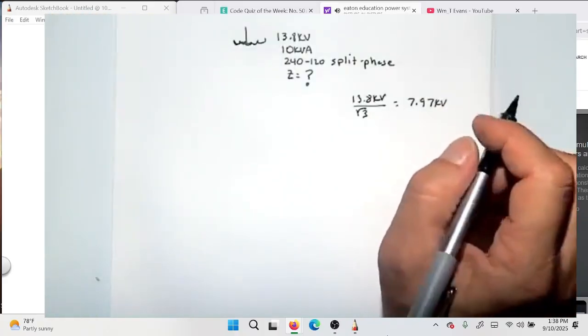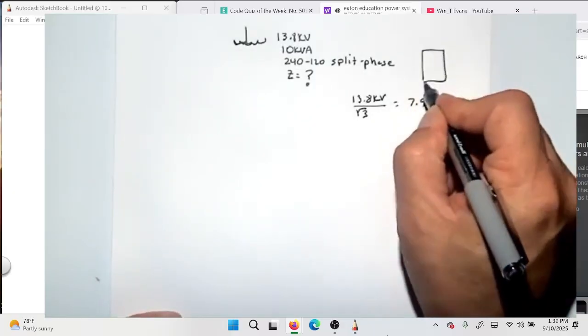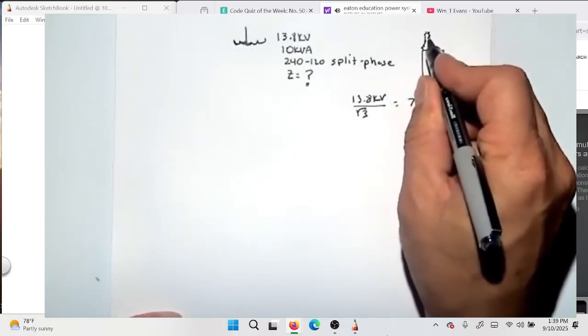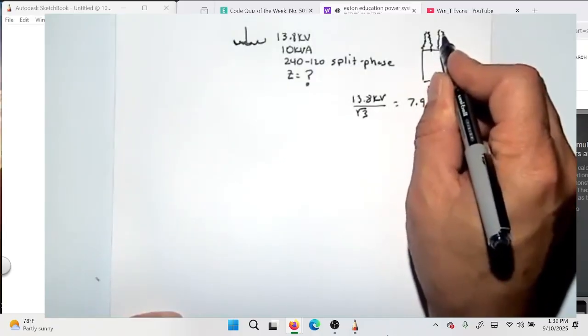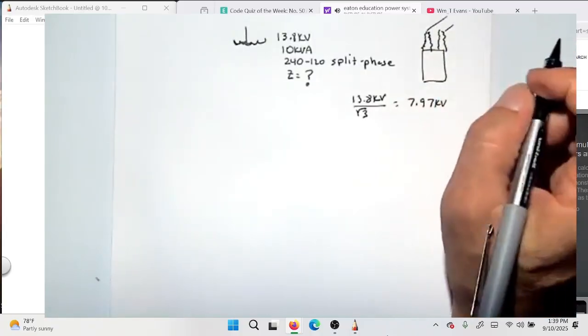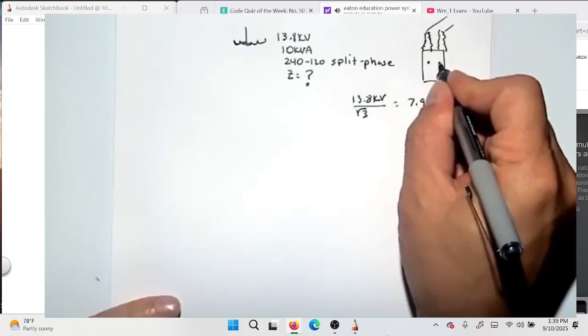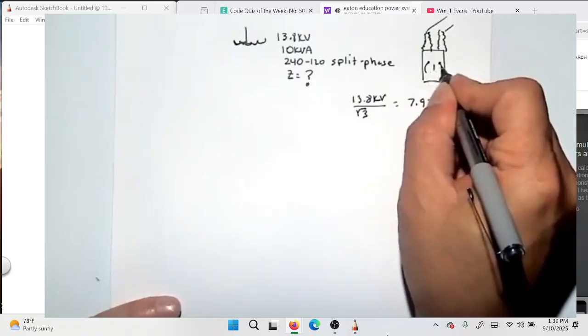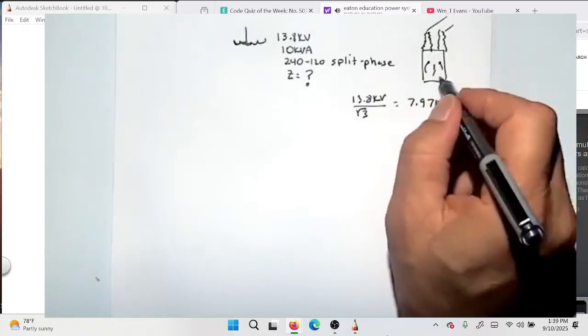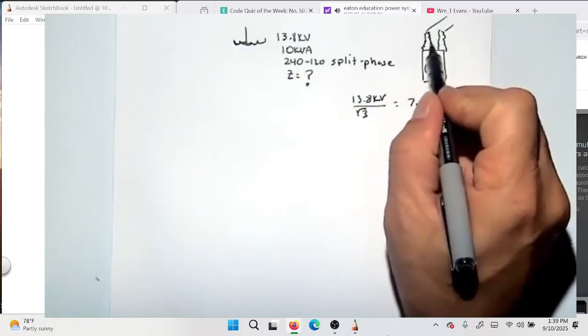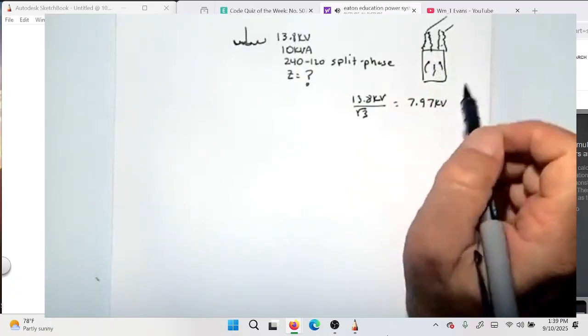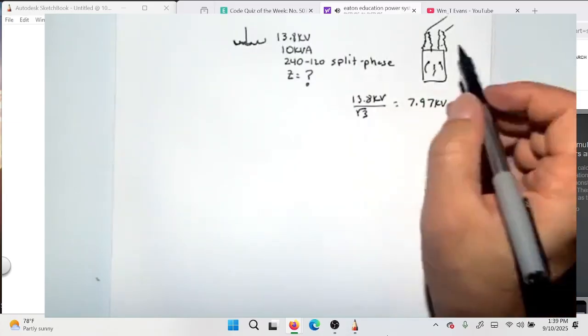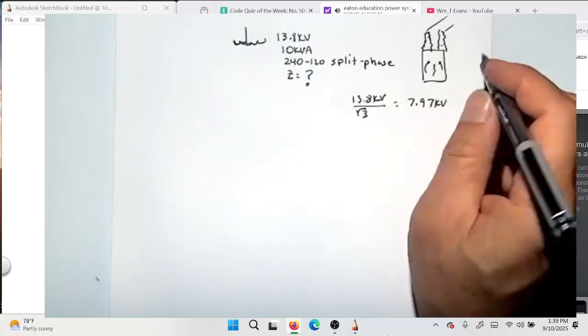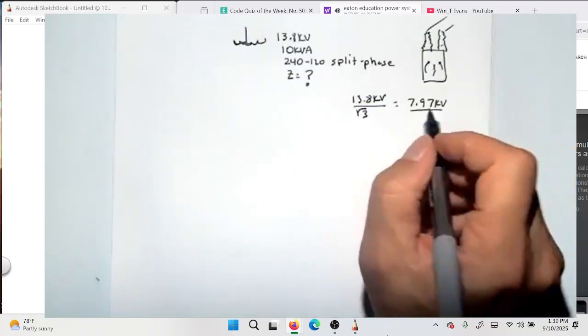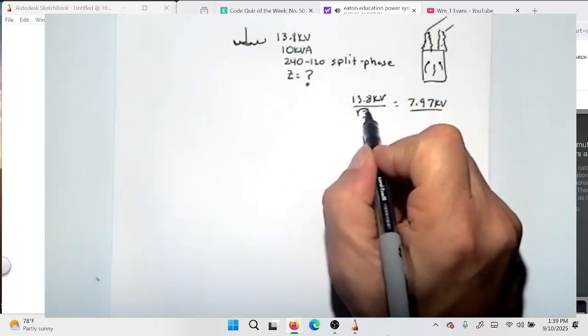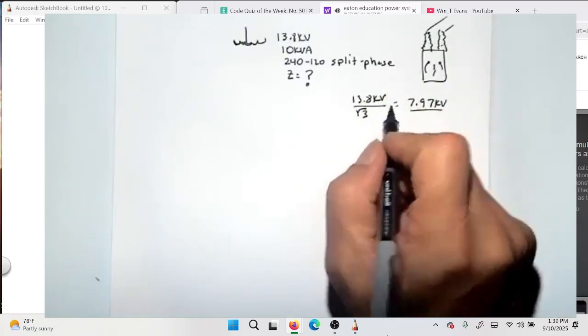But the way you can tell that is if you look at the transformer, and the transformer has 2 bushings that are about the same size. Typically, they feed them line to line. You'll see your secondary bushings coming out of the secondary here, and the 240 volt and the center tap grounded neutral is coming off there. If there's only one tall bushing and one short bushing, then a lot of times it's line to neutral. They do that because the cost of the bushing obviously adds up across the many, many transformers that are out there. So sometimes they apply them at line to neutral rating, or in this case, line to ground, and sometimes they apply it at line to line. But we're going to just say it's line to line for this one.